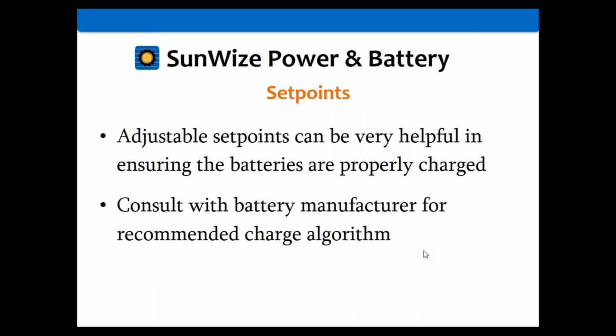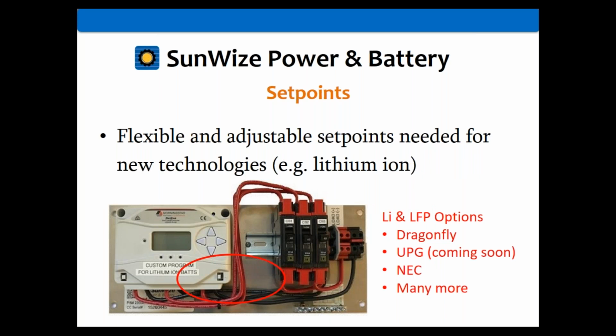Set points are very important. Adjustable set points can be incredibly helpful in ensuring batteries are properly charged, and this is becoming even more important with newer technologies. I'd also refer you to the battery manufacturer for the recommended charge algorithm, since even among valve regulated batteries, different manufacturers want different charging—AGMs and gels may differ, one wanting say 14.1 volts and another 14.3. That small 0.2 volt difference can actually extend battery life, maybe from 4 years to 5, getting an extra 10 to 20% out of the battery's life.